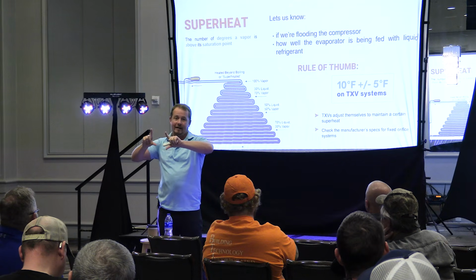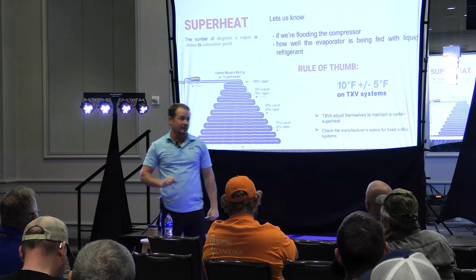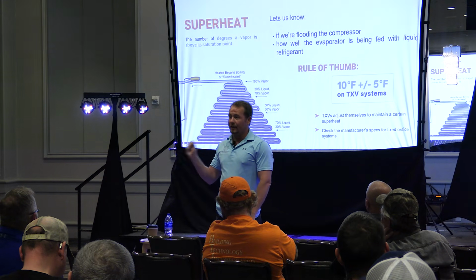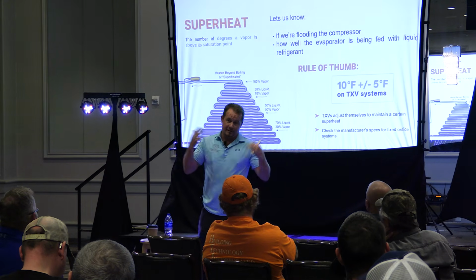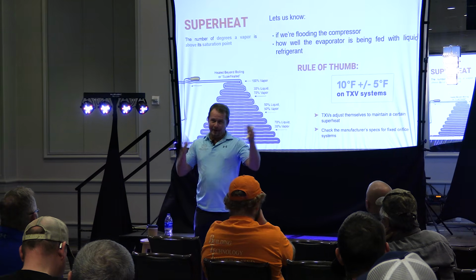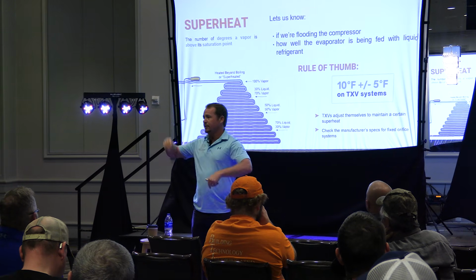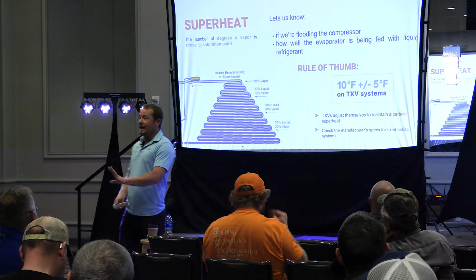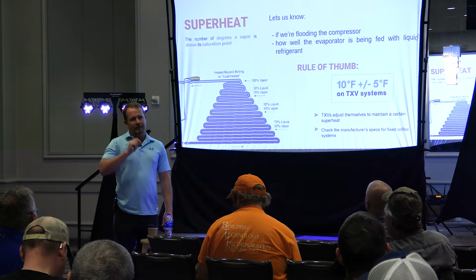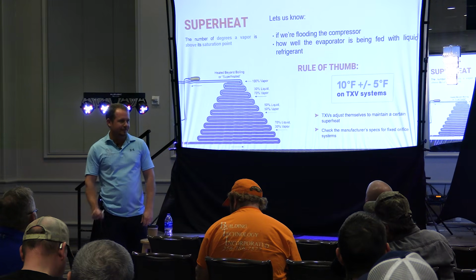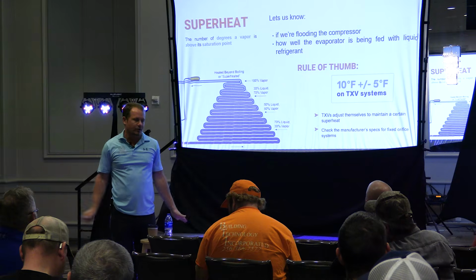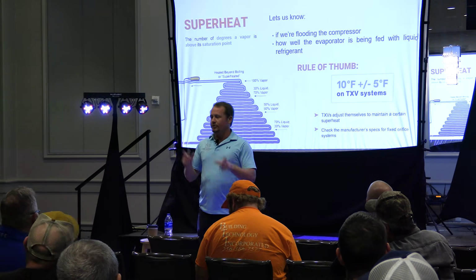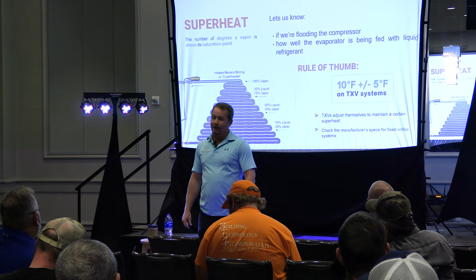And you can actually have a case where that entire assembly there is full of liquid, and you don't get a temperature drop. Because getting a temperature drop on liquid with pressure alone, see, I always thought that you did. I thought, well, and I even say this in one of my videos, decrease in pressure equals decrease in temperature. Increase in pressure equals increase in temperature. On liquid, while that is technically true, it's something like 0.00001 degree. Like it's immeasurable. You're not going to measure it. Are there cases where you could have no temperature drop across the liquid line dryer and actually have a plugged dryer?